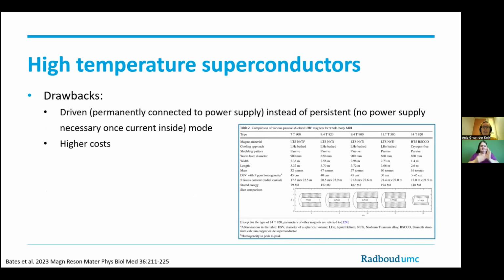There are two drawbacks. It has a higher cost, so it's just expensive, and it is driven instead of persistent mode. Driven means that it's permanently connected to a power supply, so you will continuously need a power supply. And this is the example of the 14T and the bore size. You can see with the increasing Tesla, so this is 7, 9.4 two times, and then 11.7, that the bore is becoming a little bit smaller. And this is actually a wider bore that's more similar to the 7T system. And the outside of the bore is even thinner than for the 7T.